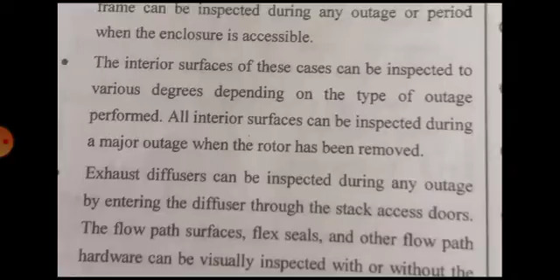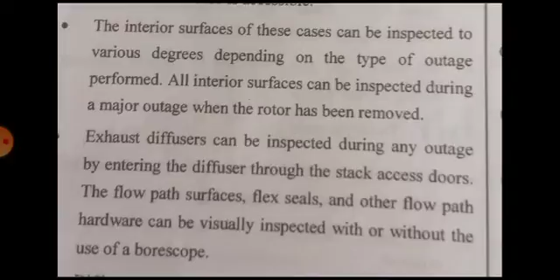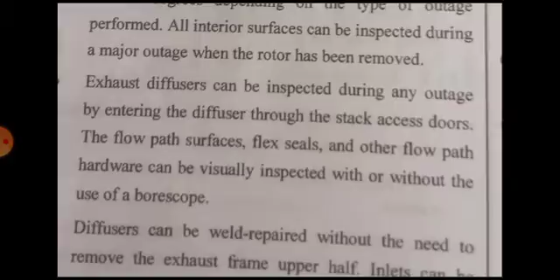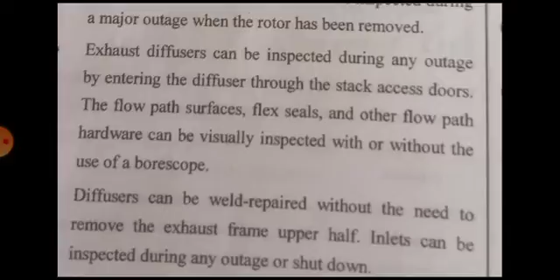The interior surface of these cases can be inspected to various degrees depending on the type of outage performed. All interior surfaces can be inspected during a major outage when the rotor has been removed. The exhaust diffuser can be inspected during any outage by entering the diffuser through the stack access door.